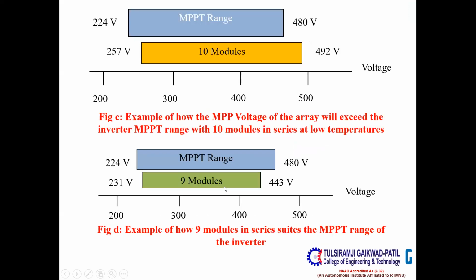In the next slide, you can see if we go with 10 modules, then the lower limit is okay, but the higher limit is exceeding 480 volt. So again, it is not advisable. So the selection would be 9 modules.